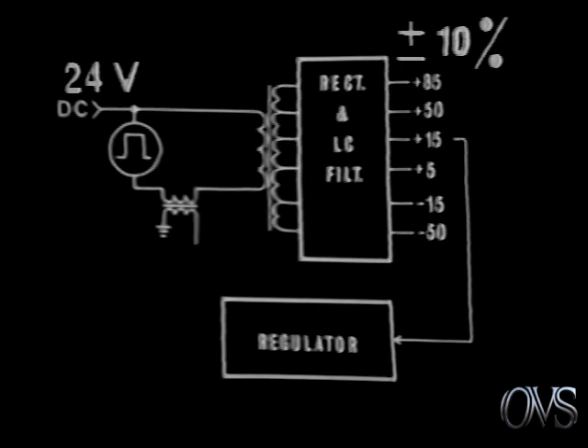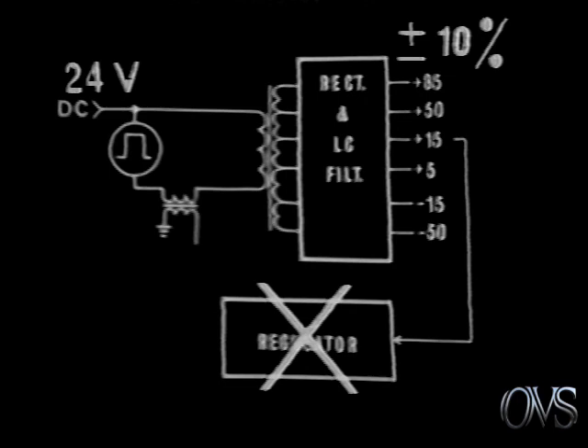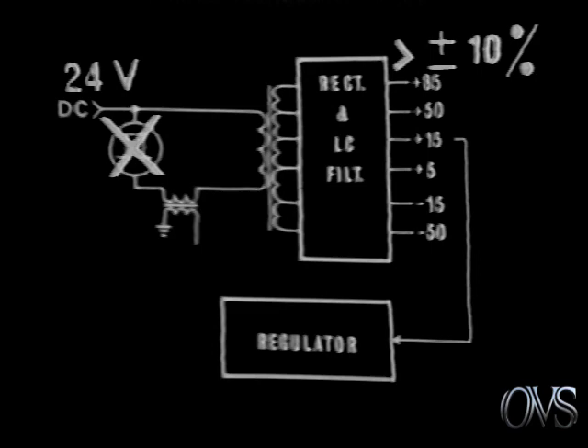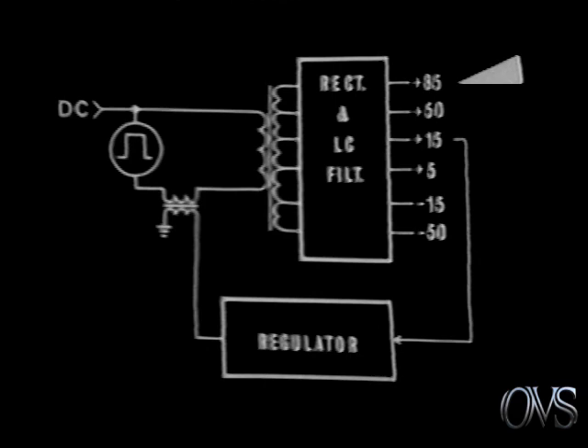All outputs out of tolerance by more than 10% indicate that the oscillator is causing the problem. If only one of the outputs is out of tolerance, check the rectifier filter for that output.